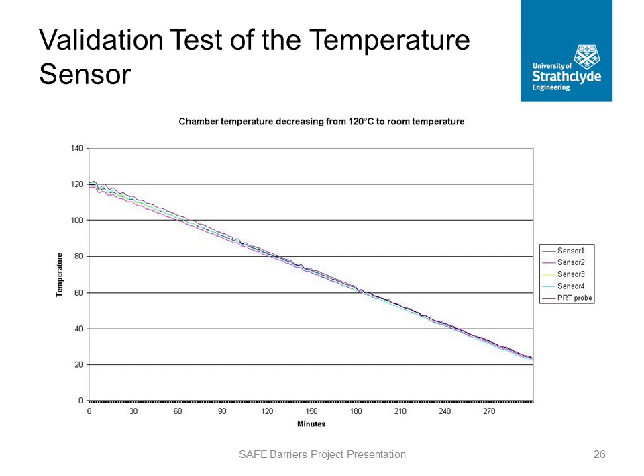This figure demonstrates the temperature measured inside the climatic chamber, where the interior temperature drops gradually from 120 degrees to room temperature. Four temperature sensors and the high-precision platinum resistance thermometers are installed inside the chamber. The measurement of temperature using both instruments is synchronized, and the measurement results are compared. In the figure, we can see that the temperature measured by the sensors and the PRT probe are in full agreement, and the discrepancy is below 0.5%. For temperature between 100 degrees and 120 degrees, the discrepancy between different instruments increases to less than 2%.